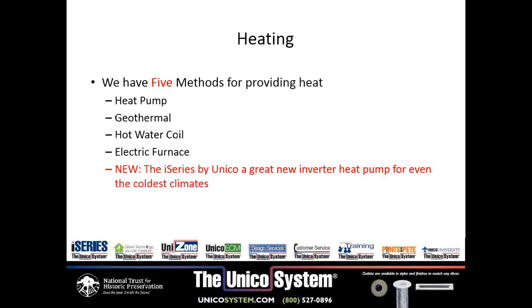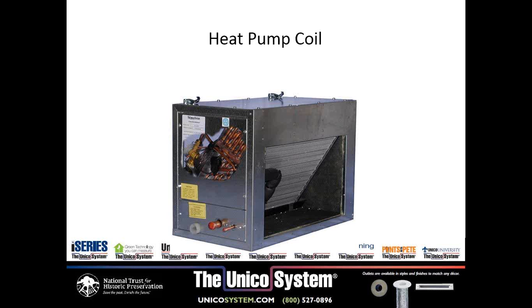So very, very efficient heating with that I-Series. So we're going to talk a little bit in depth about that. There's our heat pump coil. Now this is our TXV coil. And as you notice, it's a very thick coil. It's a 6-row deep refrigeration coil. So we can actually use 2 of these coils as accumulators. One of the aspects of heat pumps is it's a slightly different charge in the winter than it is in the summer. And so what we do with this deeper coil is we use that as an accumulator.